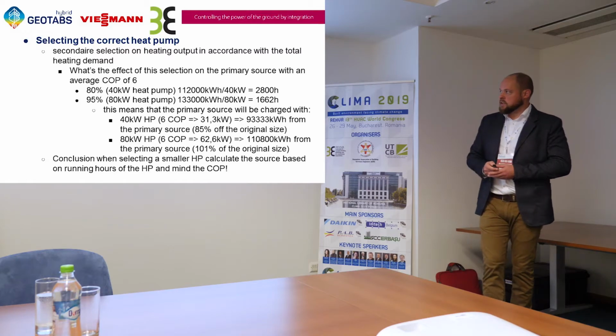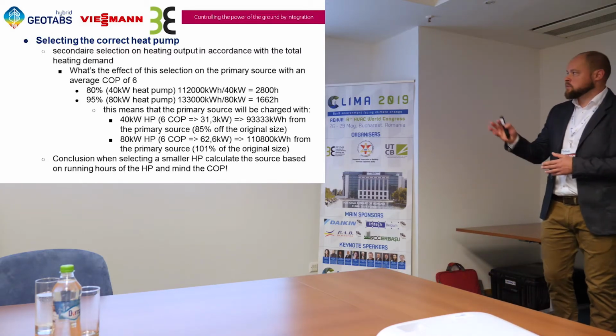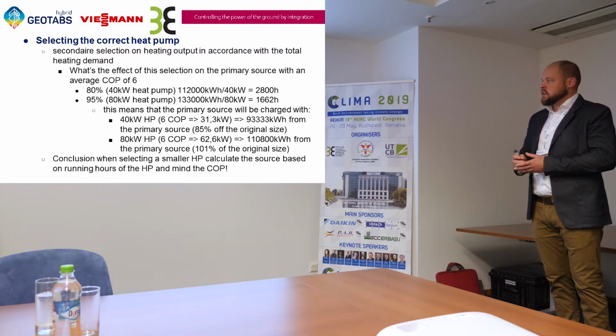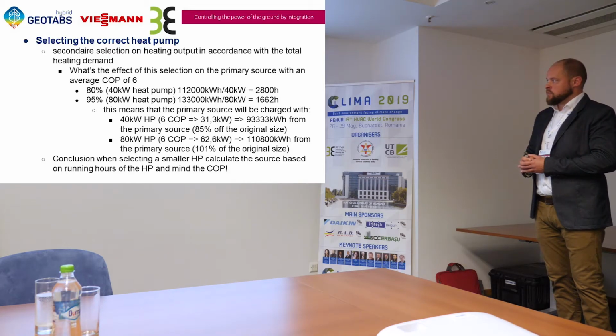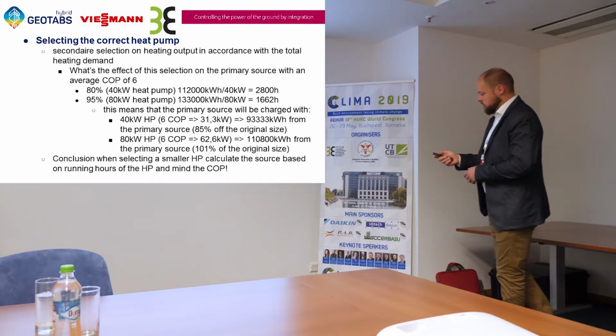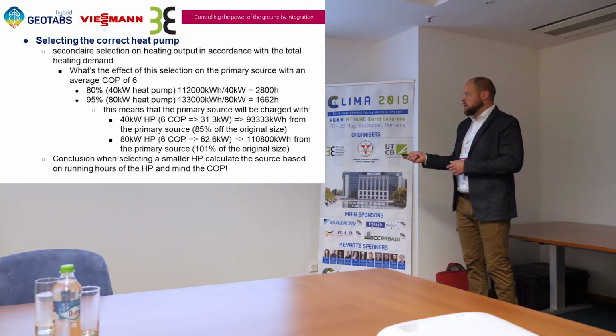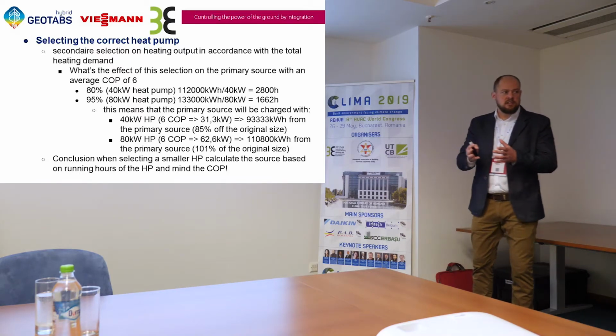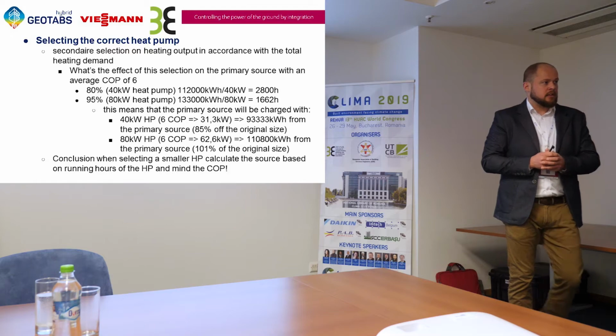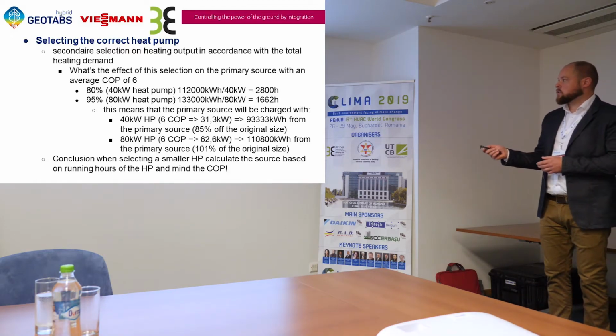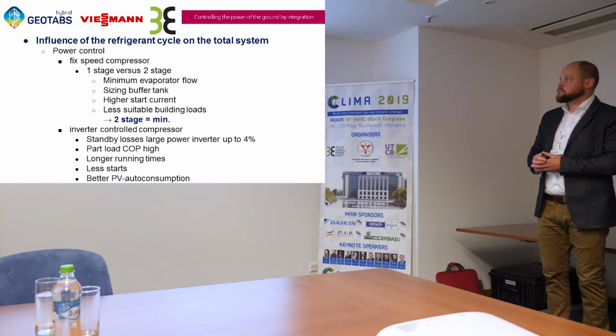So if you see here in the example, the first calculation was made with a COP of 4.6. In this example, I took the COP of 6, and you can see that with this higher COP, the load on the source is increased and even is higher than originally calculated. So you have to know the COP or the working conditions of the compressor to make a correct calculation of your source. That's very important.